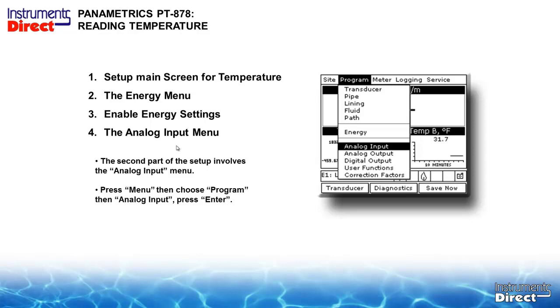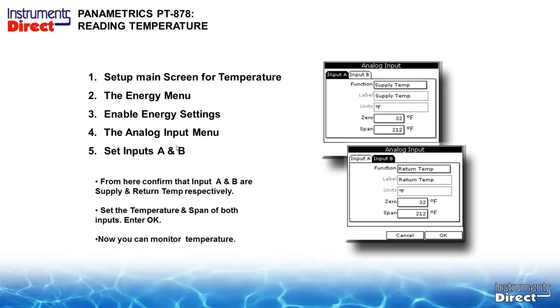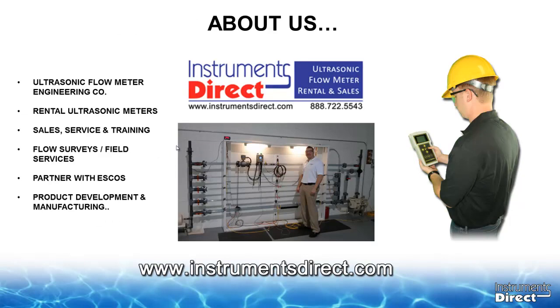Press menu, then choose program, then analog input, and press enter. From here, confirm that A and B are supply and return temperature, respectively. This is important when you have to go backwards when someone wants to look at your data. Set the temperature span of both inputs and then hit enter, and now you can monitor temperature.